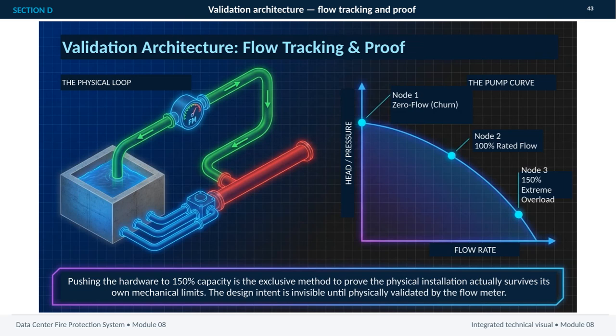intent alone. Node 1 represents zero-flow churn, showing how the pump behaves when circulation is present but delivery is effectively stopped. Node 2 is the normal reference point, at 100% of rated flow. Node 3 pushes the system to an extreme overload condition at 150%. The pump curve links these conditions through 2 key measurements, head or pressure on one axis and flow rate on the other. Together, they show how performance changes as the system is driven harder.